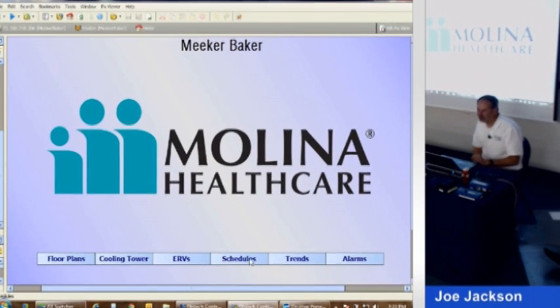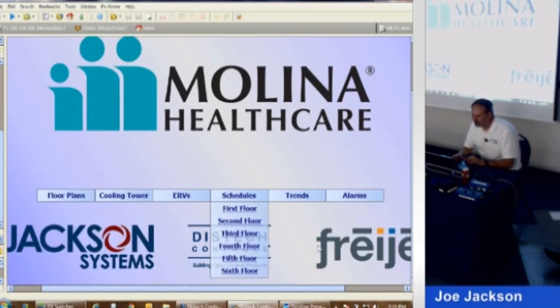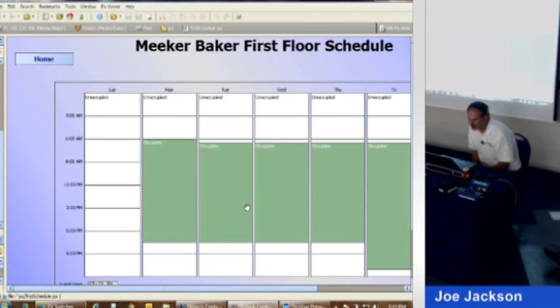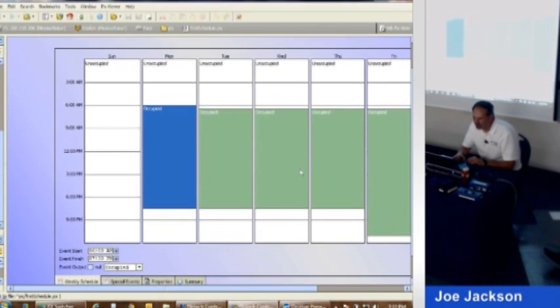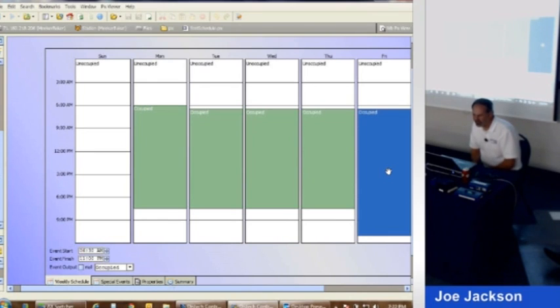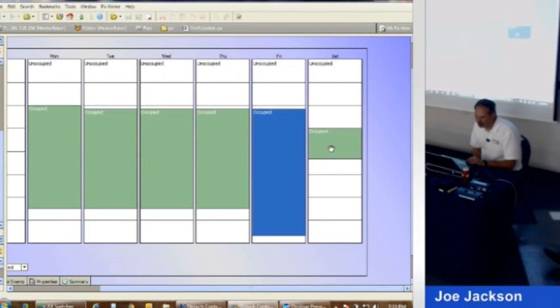Schedules are really easy in this building, on this system. Looks like they broke the schedules up by floor. We'll just look at the first floor schedule. The green part's the occupied time of day. Starts at 6 a.m. and runs till 7:30 p.m., except for on Fridays. It starts at 6:30 a.m. and runs till 11 p.m. It's unoccupied all day on Sunday. It looks like it's occupied a little bit on Saturday.